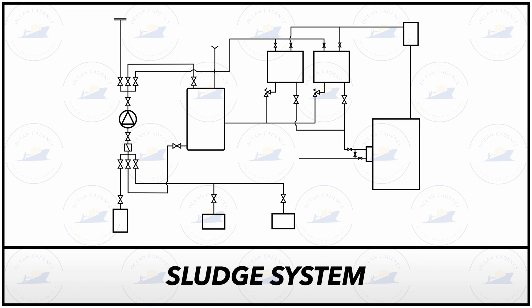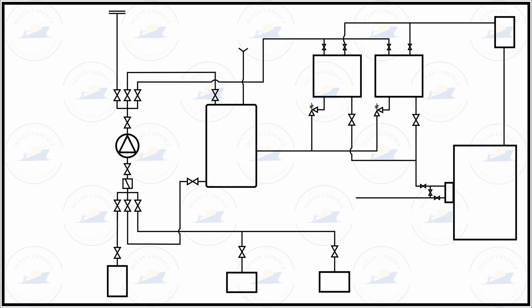Once we shift our focus on to the sludge system, we know that there are different elements through which sludge is generated on board. The fuel used in the main engine, auxiliary engine, and boiler has to be purified through the separator, and this is where the core chunk of sludge generation comes from. The scavenge and under-piston spaces, other areas within the main engine, leaks, and swept oil from the lube oil section also contribute to waste oil generation as part of sludge. Other manual draining of different elements on board also contributes to sludge generation.